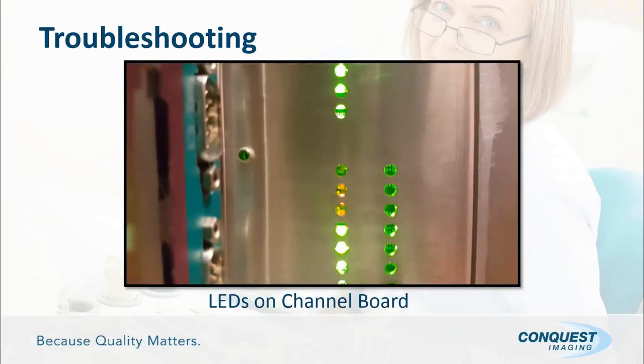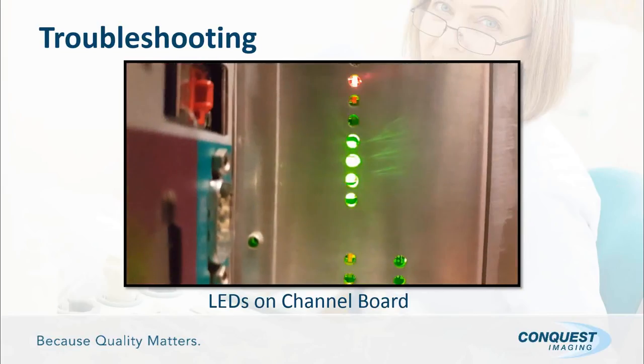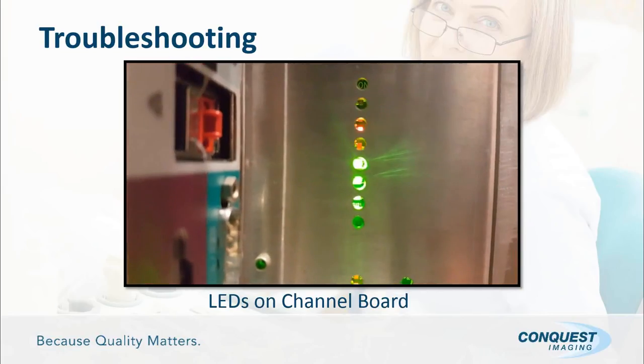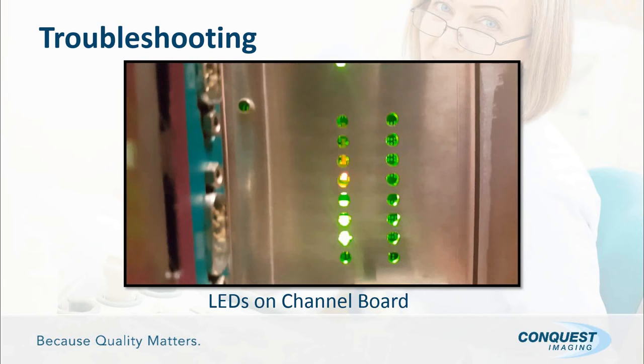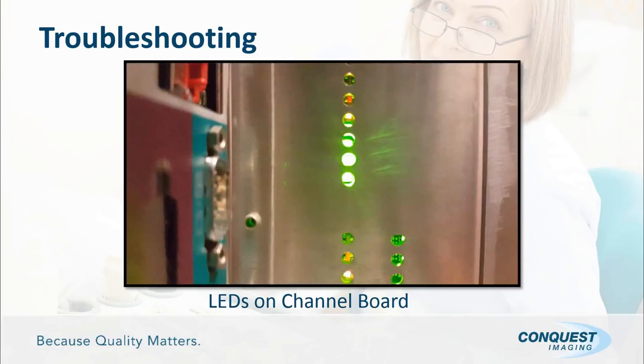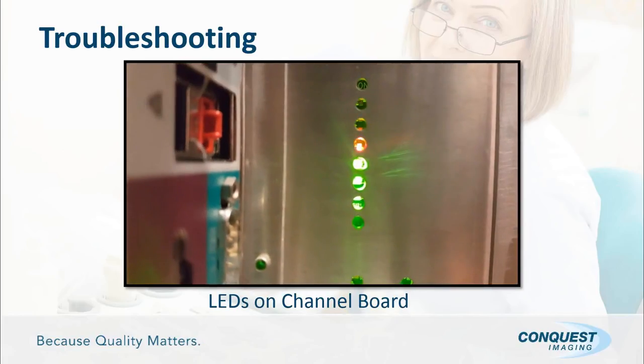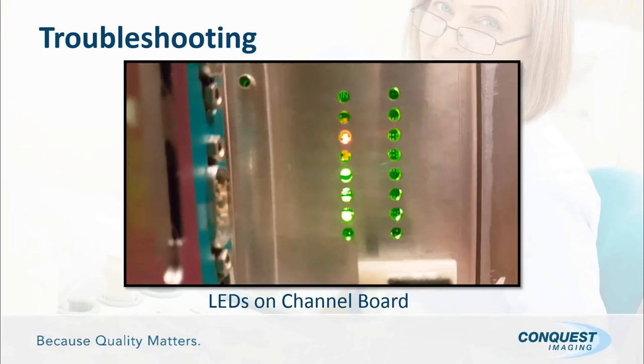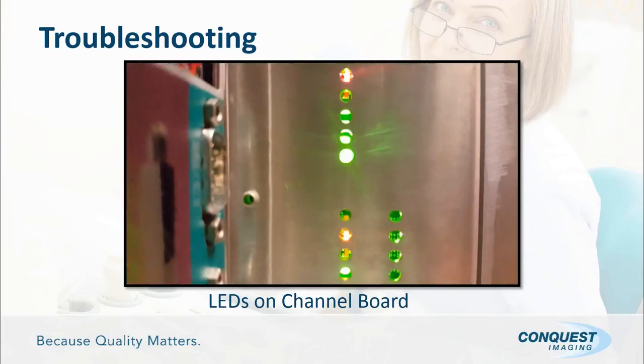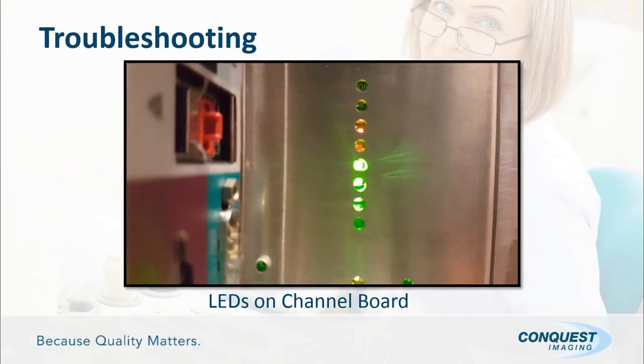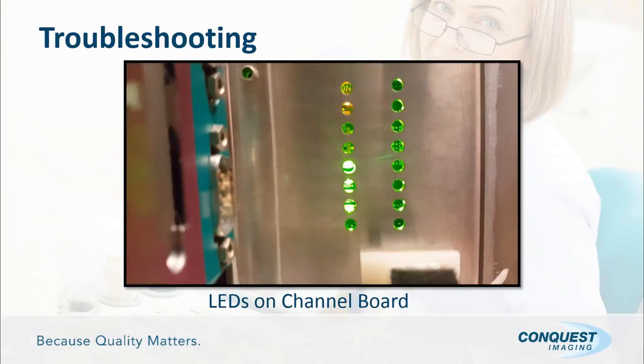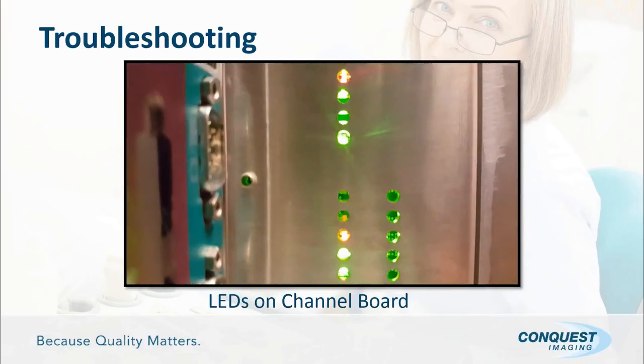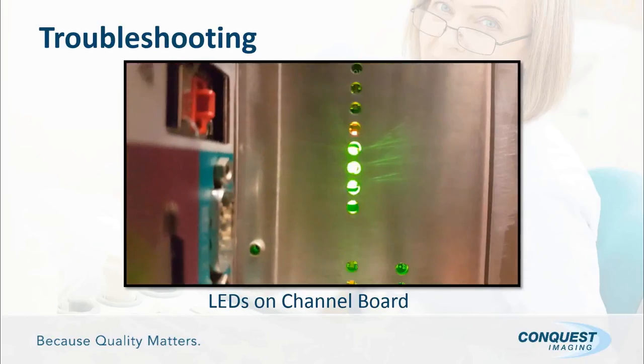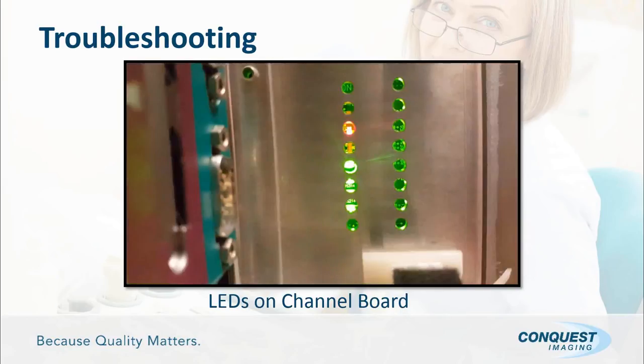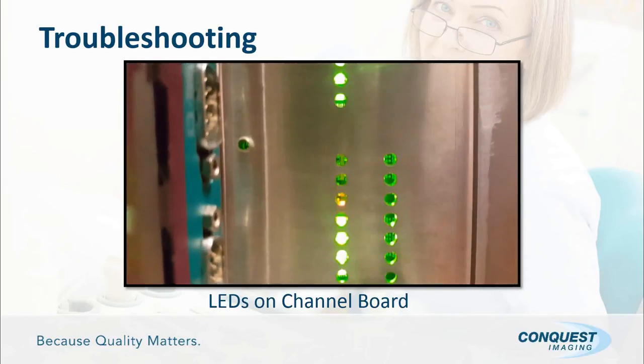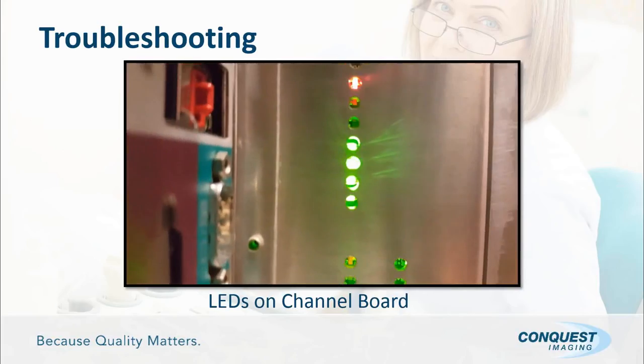This is the LEDs that are located on the channel board. Again, one of the things that are difficult about these LEDs: they're located on the left-hand side of the system as you're facing the front of the system, and they're very difficult to see because they just have a really small area into which to see them. They say you might need to use a mirror or some kind of reflective device so that you can easily see these lights. I use my camera phone, because it will fit in that slot, and I can get a much better view of what I'm looking at.